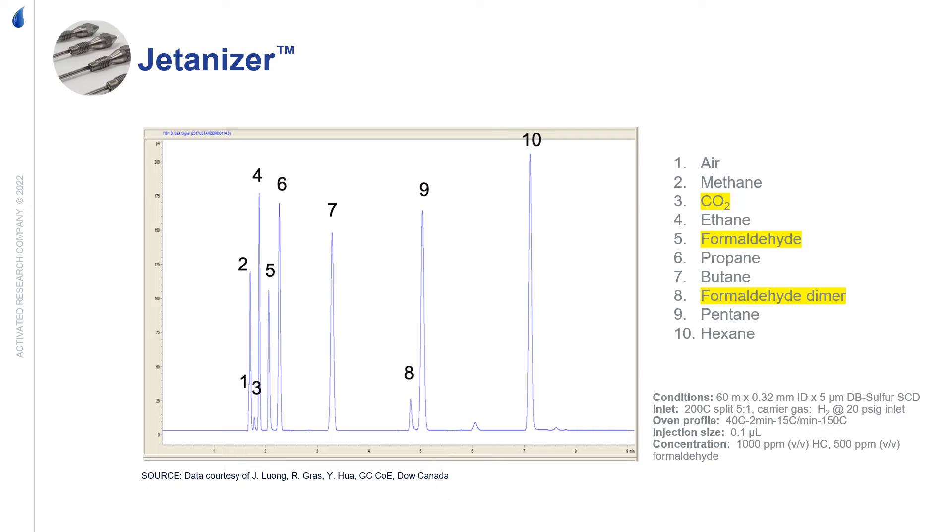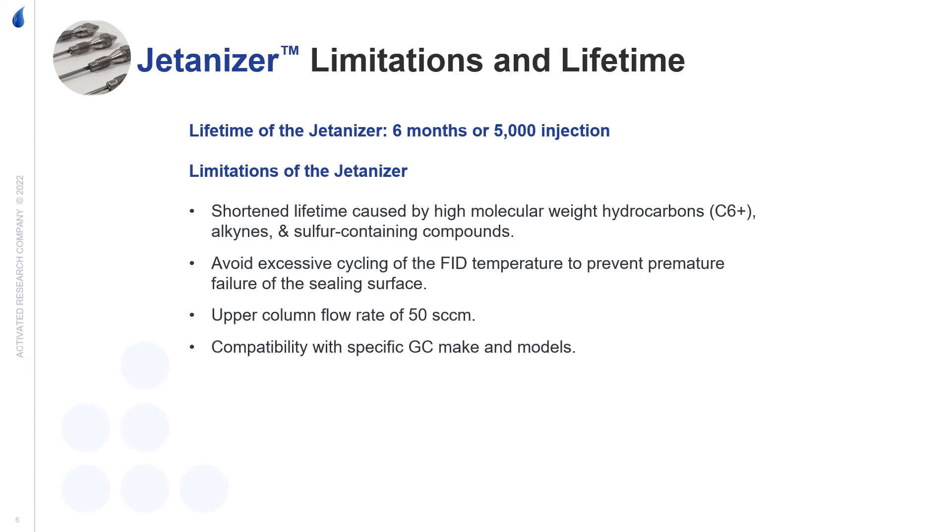Other typical uses for the Jetanizer include analyzing carbon oxides in refinery gas, natural gas, and ethylene and propylene streams. The expected lifetime is about six months or 5,000 injections. High molecular weight hydrocarbons, alkynes, and sulfur will shorten the lifetime of the Jetanizer.